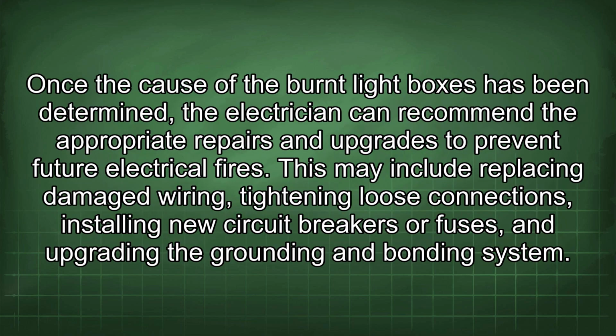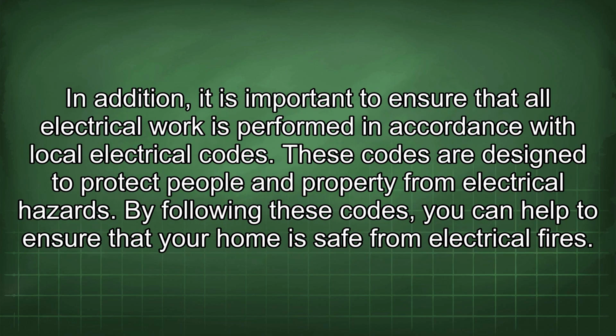Once the cause of the burnt light boxes has been determined, the electrician can recommend the appropriate repairs and upgrades to prevent future electrical fires. This may include replacing damaged wiring, tightening loose connections, installing new circuit breakers or fuses, and upgrading the grounding and bonding system. In addition, it is important to ensure that all electrical work is performed in accordance with local electrical codes. These codes are designed to protect people and property from electrical hazards. By following these codes, you can help to ensure that your home is safe from electrical fires.